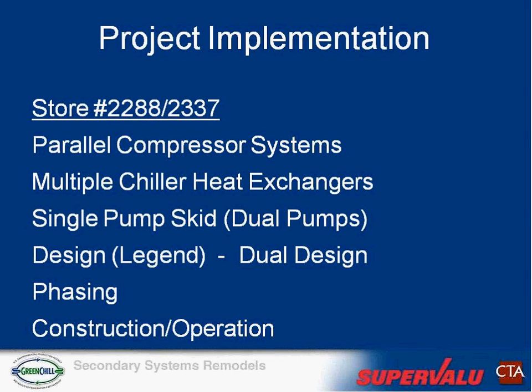Again, phasing was important. Here it was a little bit different. We had an existing rack running, existing DX medium temperature systems. When everything was piped up, ready to go, and charged with glycol, we basically took a lineup off and started up a new lineup. We kind of just transitioned the load with the systems. Now we had 3 different chillers, so we had some staging. Each one of them has staging capacity with the multiple compressors, but then having 1, 2, or 3 of them on gave us some staging capacity too. I don't know if it was any easier doing it with the parallel racks, but it was just a little bit different.